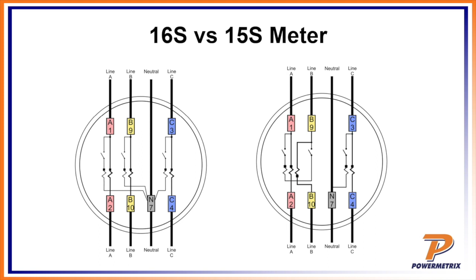Back on the PowerPoint, if you look at the left-hand side, that's a 16S meter. Notice your A, B, and C potentials, or phases, reference a neutral phase on pin 7. Now on the right, different story. You still have 3 elements in the meter, and it looks identical element-wise, but it's wired totally differently. Notice both A and B reference each other, they don't have a neutral phase, and you've only got a C reference on itself. We'll explain why they do that.